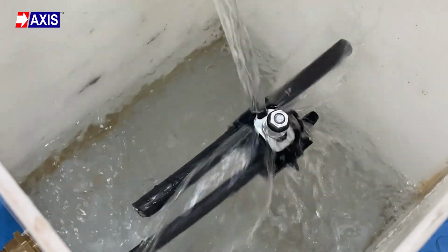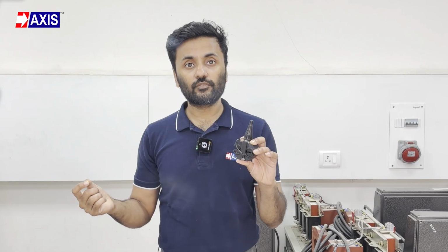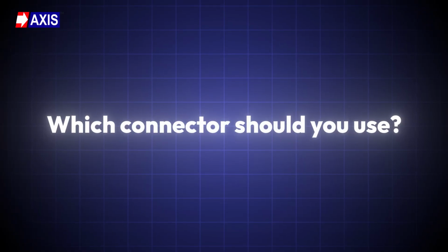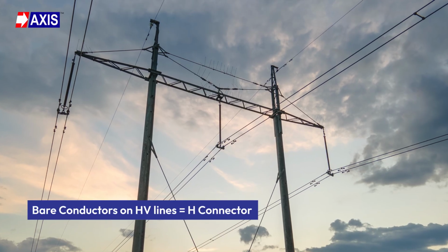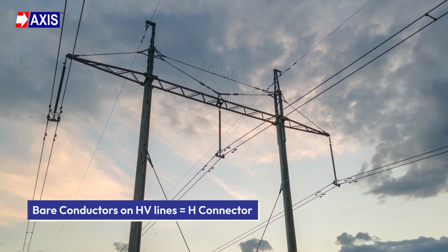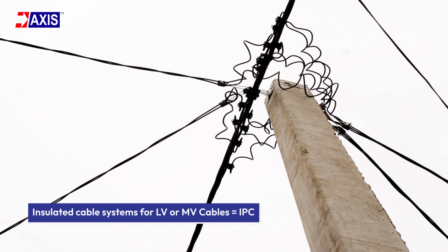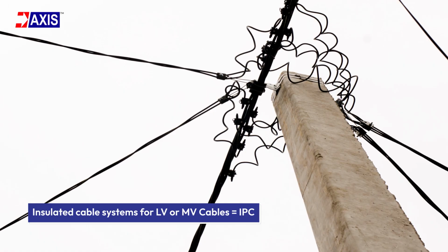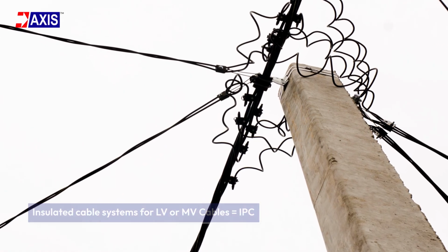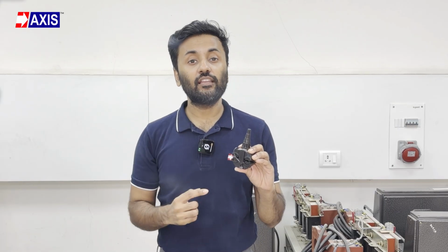This is why IPCs have become critical in modern distribution systems. So, which connector should you use? For bare overhead conductors on high voltage transmission lines, you need an H connector. The conductors are already bare, mechanical strength is a priority, and these are mainline splices carrying heavy loads and handling tension from wind and conductor weight. But for any insulated cable system, whether low voltage AB cables or medium voltage covered conductors, you need to use an IPC. The factory sealed connector protects the entire system from water ingress. Installation is faster, safer, and you eliminate the risk of cable failure.